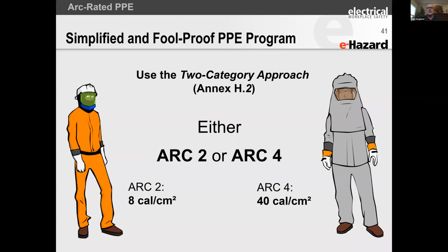Most companies use an arc level 2 or a category 2 and a category 4 garment setup, and this is a good way to do it. If you wanted to stick one in the middle at about 20 calories, that would keep you out of the flash suit or as heavy of a flash suit more frequently. But this is really the best way to do it. Layering up can really add a lot of value because you can put a coverall over top of your 8. And if you match it up right, it typically works out to be around 20 to 25 calories with just adding a coverall to your 8-calorie uniform.